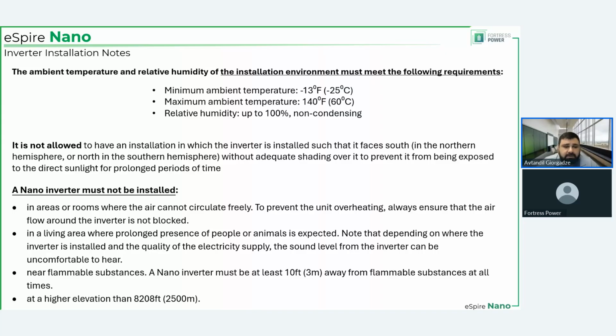Other things about what not to do: there should be adequate air circulation because, again, this is an air-cooled unit and air has to circulate around it. Otherwise, it's going to create its own microclimate, so to speak, and warm up the air around it if it's in a small electrical room. And the more it tries to cool itself, the more it increases the temperature of the air around it, right? So air circulation is a must.